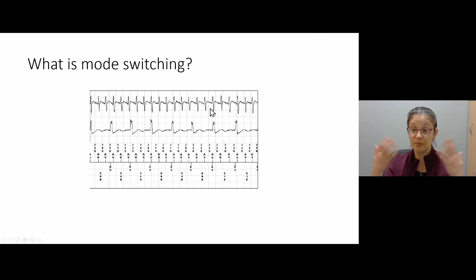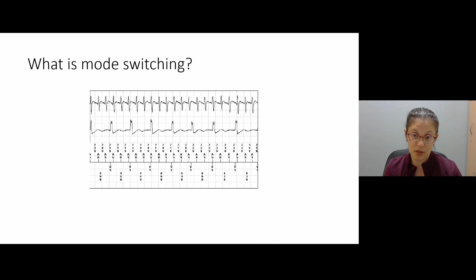Now, the way that we prevent the device from trying to pace every one of those flutter waves is twofold. One is that we program an upper tracking limit for the device so it can't pace any faster than whatever we set, say 110, 120 beats per minute. But we also tell the device if the atrial rate goes too fast, and that could be over 150, over 170, whatever rate we've set, I want you to switch from DDD to a non-tracking mode. I want you to switch back to VVI mode, for example, and it'll keep doing that until the atrial arrhythmia episode is over.